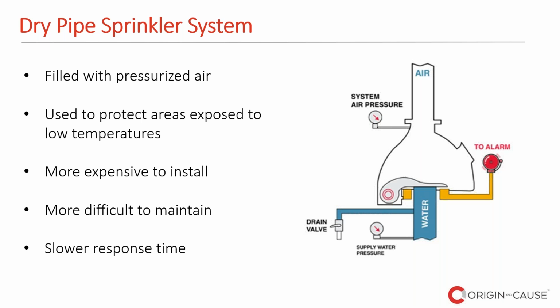As I mentioned before, these systems are very commonly used in parking garages and outdoor spaces. And the way it works is once the sprinkler head detects the fire, it bursts, and then air starts to escape. The air pressure in the system starts to drop, and then at some point, the valve opens, allowing water to come in and extinguish the fire. I usually receive claims related to dry systems during the wintertime, when freezing occurs in the pipes that were either not properly drained, not properly maintained, or not inspected properly.